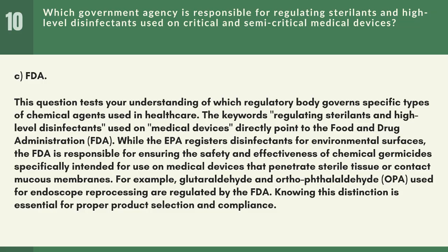While the EPA registers disinfectants for environmental surfaces, the FDA is responsible for ensuring the safety and effectiveness of chemical germicides specifically intended for use on medical devices that penetrate sterile tissue or contact mucous membranes. For example, glutaraldehyde and orthophthalaldehyde, OPA, used for endoscope reprocessing are regulated by the FDA. Knowing this distinction is essential for proper product selection and compliance.